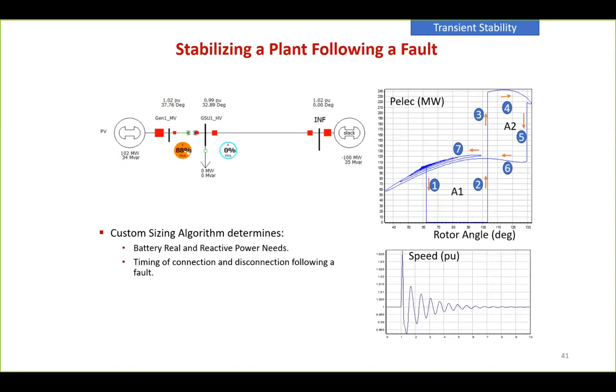In the West, a lot of the N-1 constraints that impose congestion are transient stability constraints, so it's an attractive application. As a parenthetical comment, if the mid-Atlantic coast adopts a lot of offshore wind, transient stability will become an issue where it isn't one today, because of the lack of inertia you get with inverter-based resources. So the transient stability application of storage will become a concern in PJM.